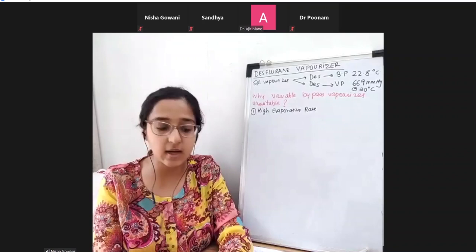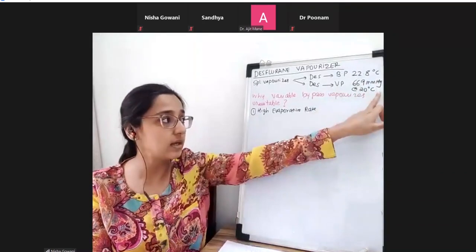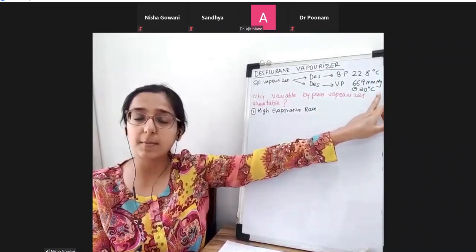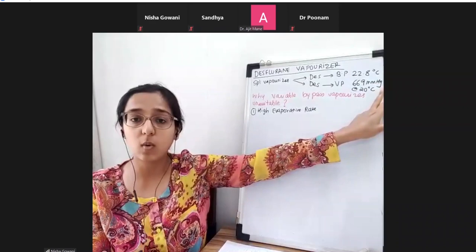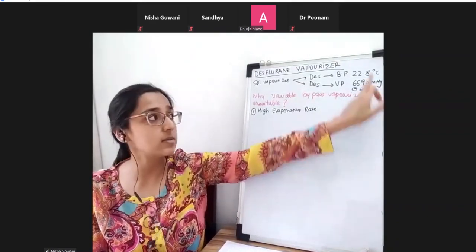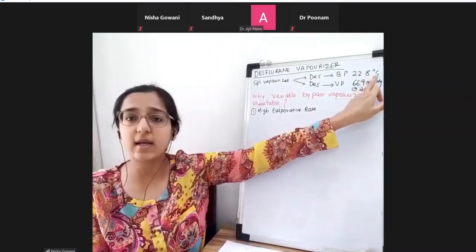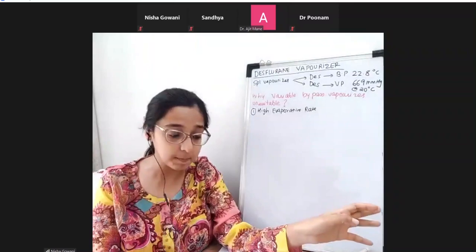Okay, so desflurane has got what? A vapor pressure of 669 millimeters mercury at 20 degrees Celsius. Okay, this is the vapor pressure, which is very close. 669 is very close to what? 1 atmosphere, 760, right? It's very close to that number. So it starts boiling at 22.8 degrees. So because of this property, we need a specialized vaporizer.